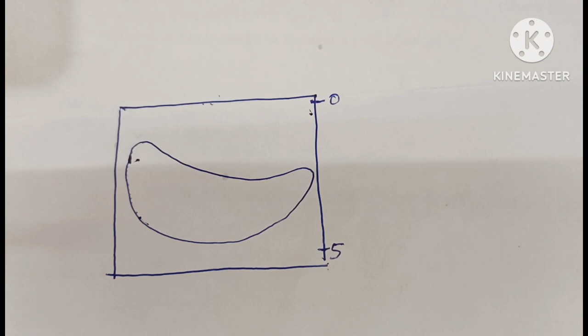Remember, at last I am telling you, there is a knob present on the ultrasound monitor. You have to find out where the depth knob is present. By rotating clockwise or anti-clockwise, you will increase the depth and decrease the depth. By decreasing the depth, you increase the clarity, resolution and frame rate, so a better image will be produced. Remember, keep your depth as minimum as possible.